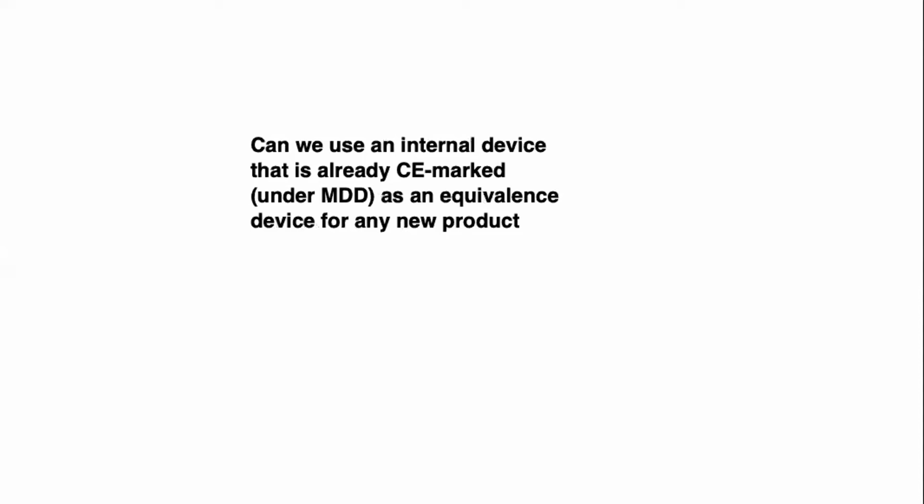And that's an exercise that you should also be very careful with, because equivalence has changed a great deal in the last couple of years under the upcoming MDR requirements and certainly MedDev Rev 4. And it is a point-by-point comparison of clinical, technical, and biological attributes that must be directly compared, and any change between one or the other must be explained and justified that it has no clinical impact or what the clinical impact may be.